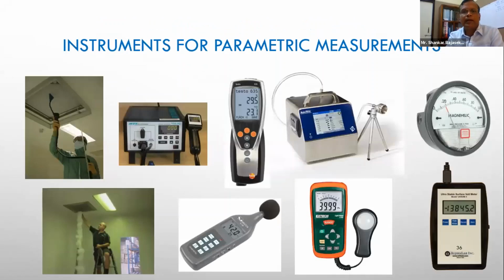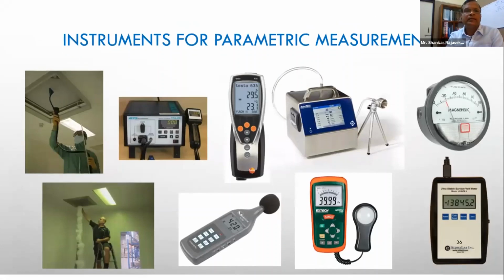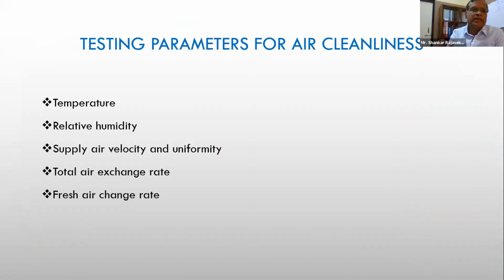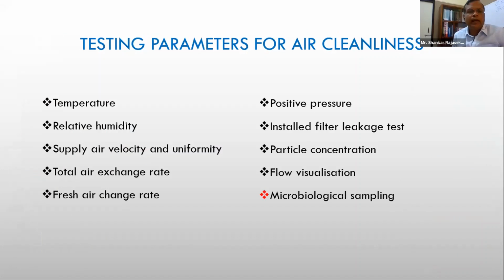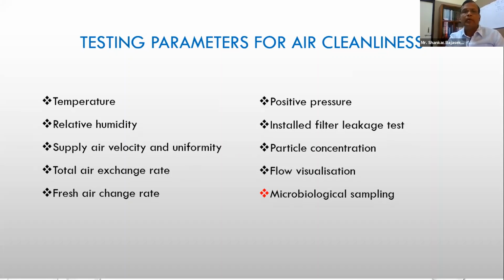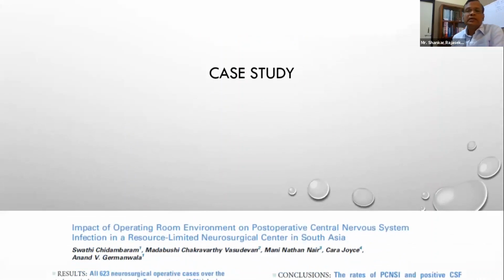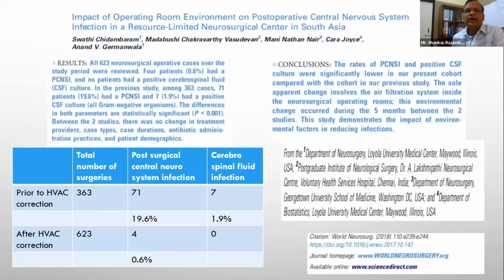So we can use lots of parametric measurements for testing for air cleanliness. At minimum these are required: temperature, RH, supply air velocity, uniformity, total air exchange rate, fresh air change rate, positive pressure, installed filter test, leakage test, particle concentration, flow visualization, and microbiological sample.